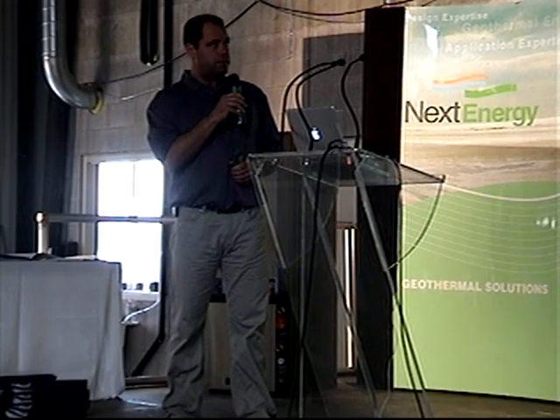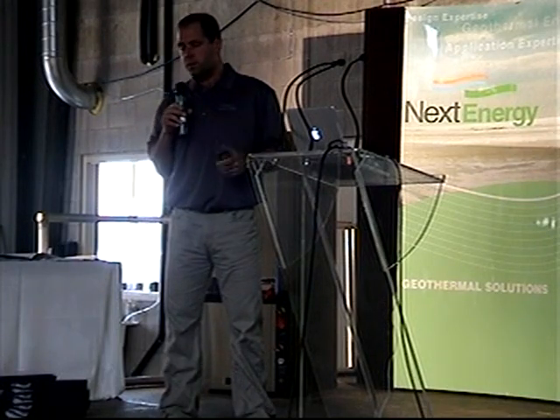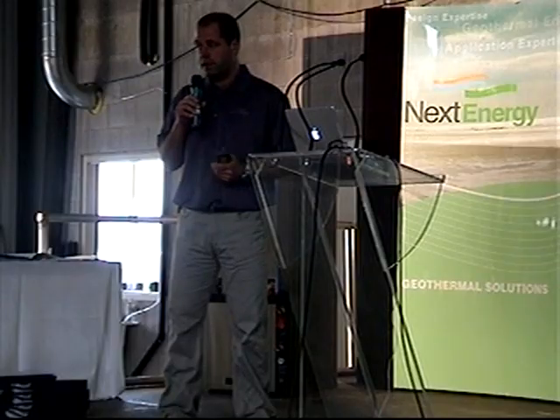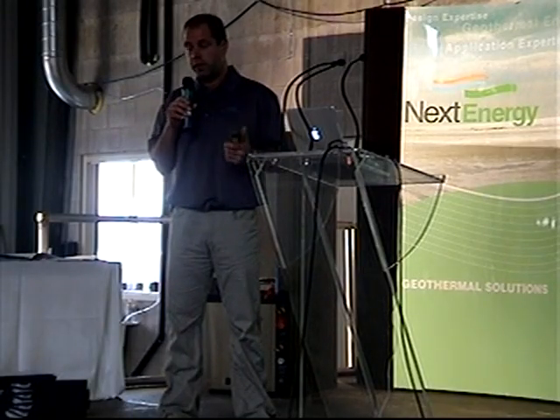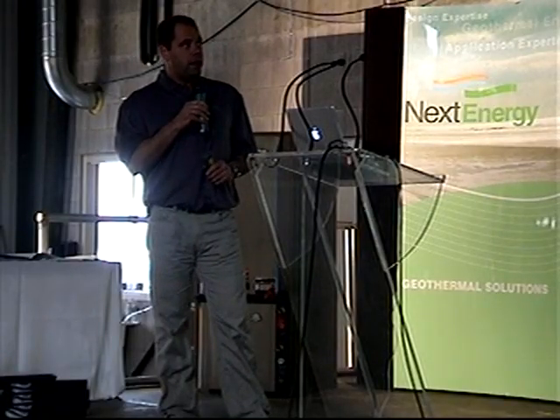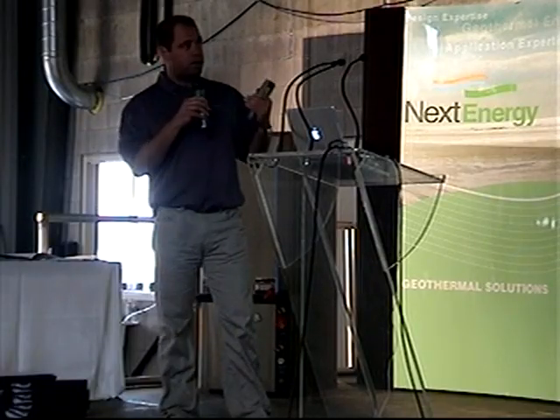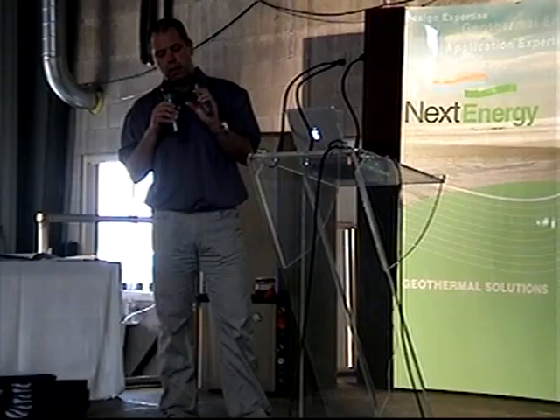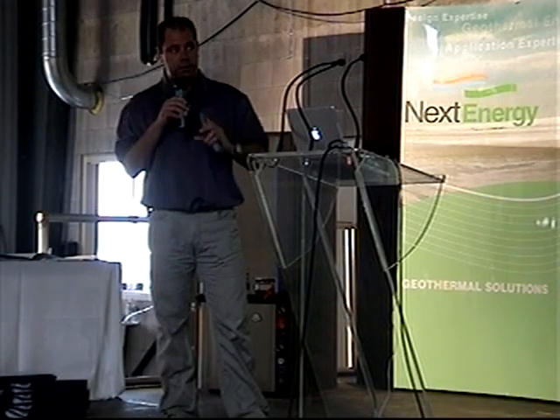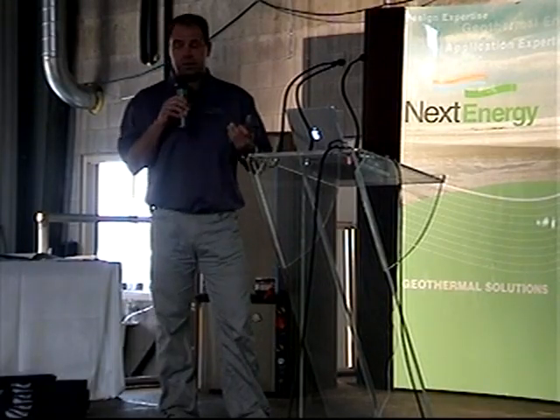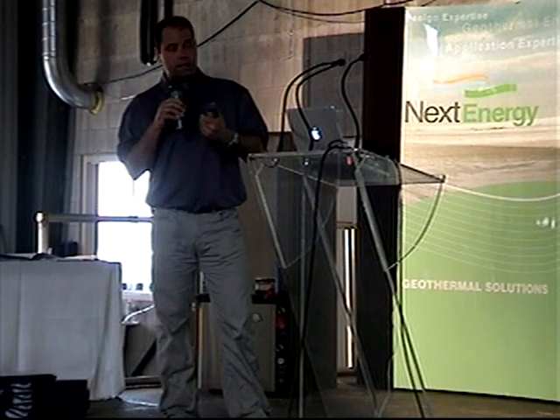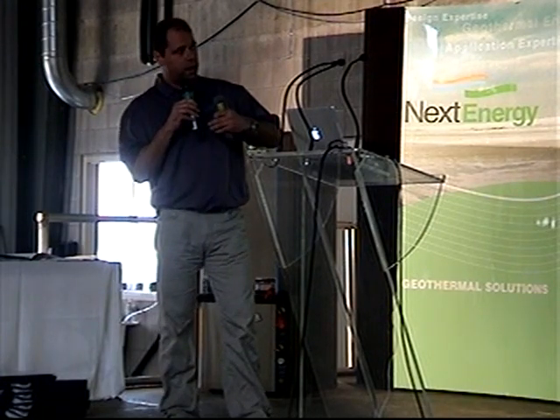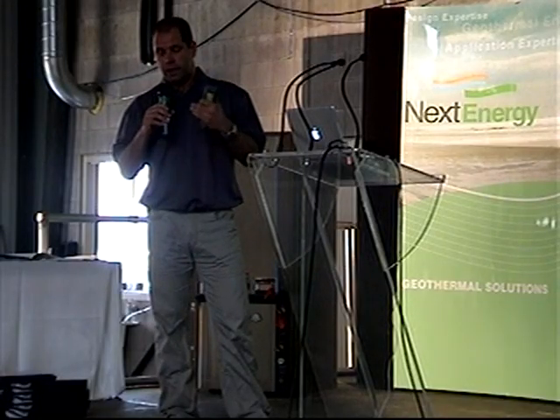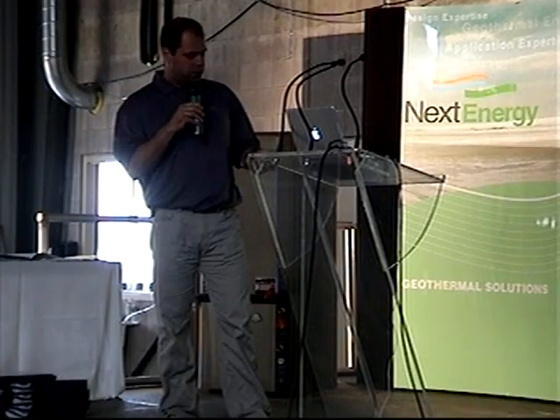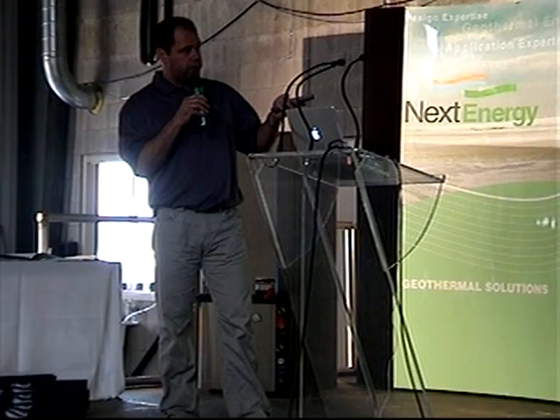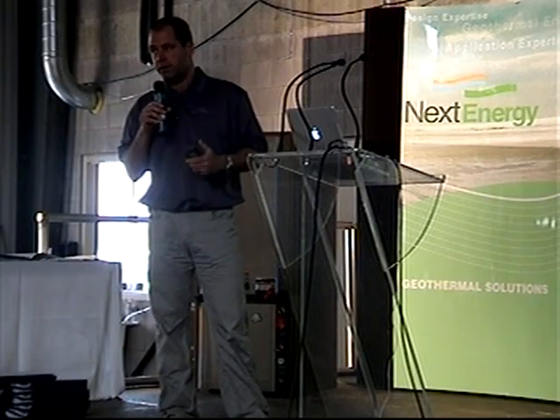So, TX valve. TX valves in our units are not adjustable, and from my experience, TX valves really never need to be adjusted. I don't think I've ever adjusted one, and when I have, I've always made it worse, so that's why they do that. On the TX valve, there's a spring in the bottom, and it works off spring pressure, and if you've noticed on those units, there's a little copper bulb fastened to the suction line. Well, that bulb has a refrigerant charge in it. I'm not sure what type of refrigerant, they're all different, but what it does is it senses the temperature of your suction line, and because it's full of refrigerant, that temperature will indicate a pressure. That pressure will open your TX valve. See right here? It'll force that piece down, allowing more refrigerant through the TX valve and into the evaporator.